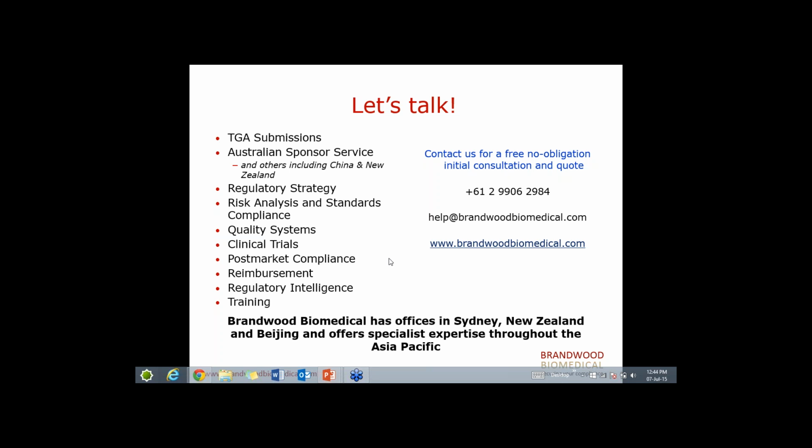Okay, there's a question on how do we know if the device will require an application audit? So for classes that are class 1, non-sterile, non-measuring, it's basically self-declared. So you submit your device application and usually within an hour you can get an approval. For classes up to Class 2B, TGA selects the application audit randomly, and this is usually based on their current concerns about particular groups or categories of devices. These can change from time to time, so sometimes they could look at a specific keyword, like software or something, but as I mentioned, it is a random application audit.